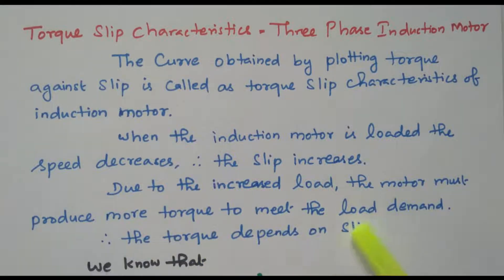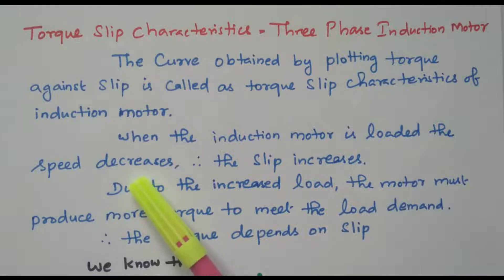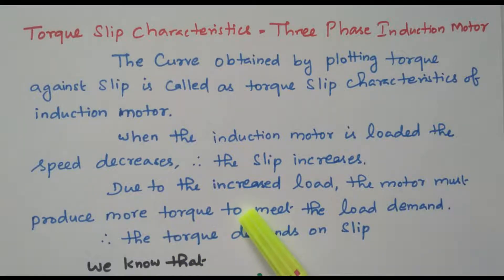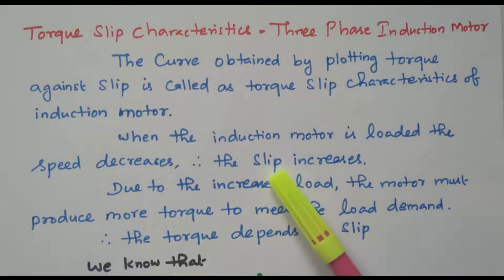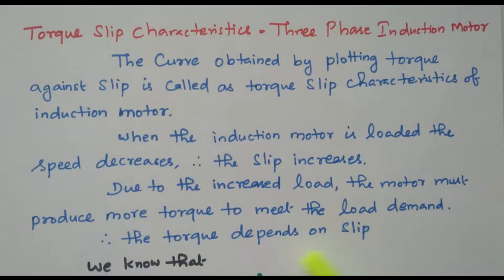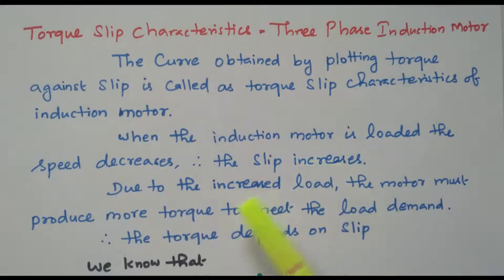But due to increased load, the motor must produce more torque to meet the load demand. So while loaded, speed decreases, but the motor will try to meet the required demand by producing more torque. So as slip increases, torque also increases — torque depends upon the slip. When loaded, speed decreases, slip increases, and at the same time, in order to meet the load, torque also increases. All are interrelated.